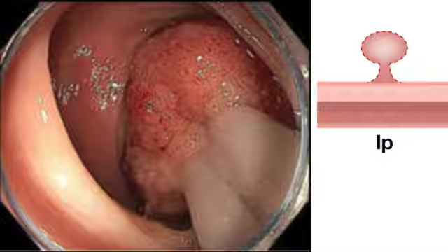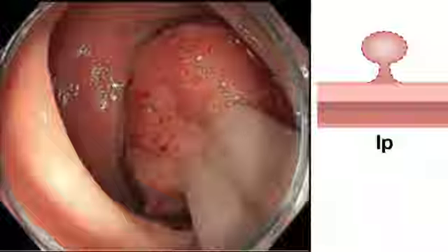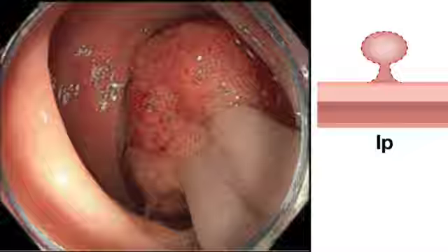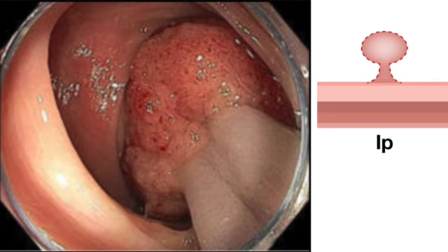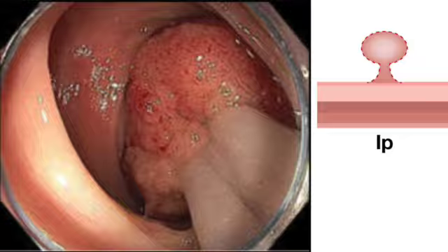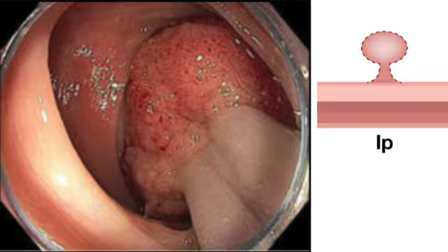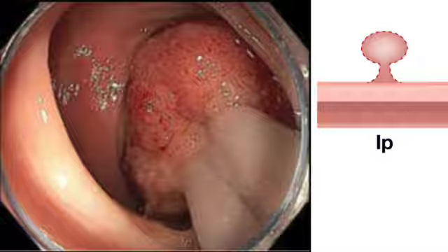It sticks up. But sticks up feels so subjective, doesn't it? I mean, you're looking through the fisheye lens of an endoscope. How does a doctor know if it's protruding enough to be a Is versus something flatter? That's a great question. The optics can be very deceiving. So Dr. Raju points out this incredibly practical tool they use for standardization. Which is? The biopsy forceps. The little claw tool they use for samples. Right. It's not just a grabber, it's a ruler. The closed cups of a standard forceps have a known diameter, usually about 2.4 millimeters. So they actually use it as a reference scale. They literally slide the closed forceps right up next to the polyp for a side-by-side comparison.